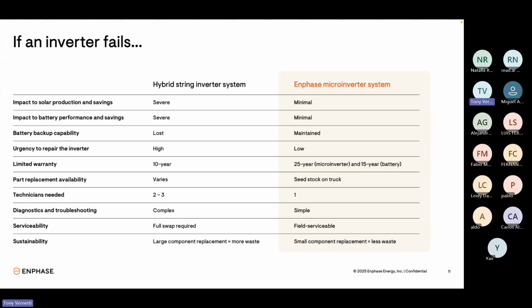Enphase systems can typically be repaired with just a single person because you're dealing with small parts as opposed to a 300 or 400 pound hybrid battery inverter unit. Enphase troubleshooting and diagnostics are much easier because we have Enphase Enlighten monitoring and microinverters, so we can actually monitor each individual microinverter in the entire system. Our systems are also field serviceable. If a microinverter or even a circuit board inside one of the units fails, it can be replaced on site. Typically, hybrid inverter systems require the entire hybrid inverter unit, sometimes coupled with a battery, to be replaced.